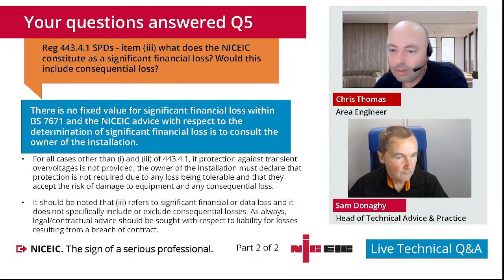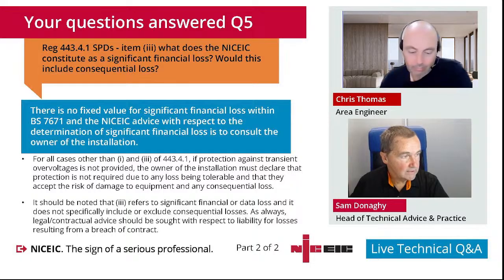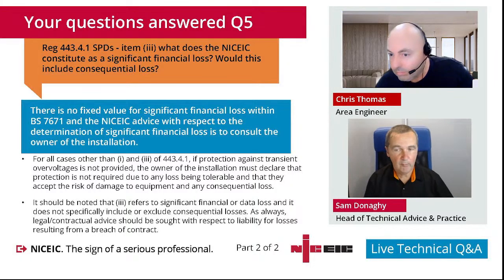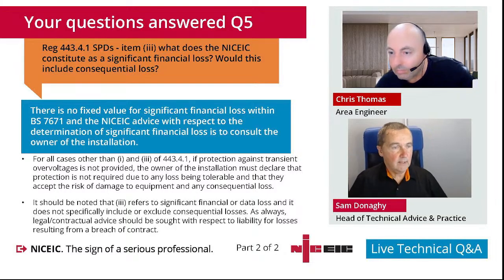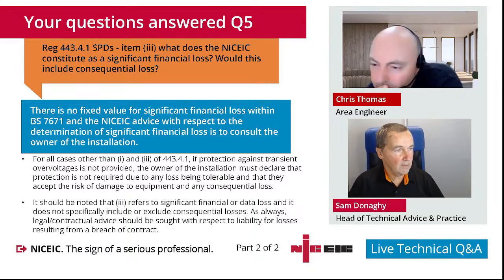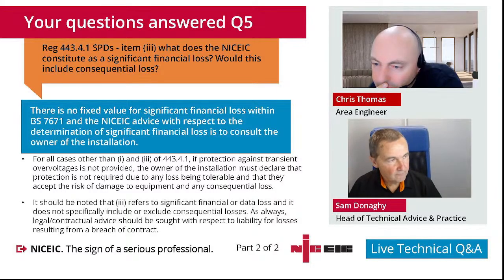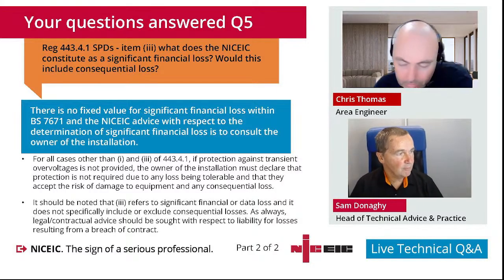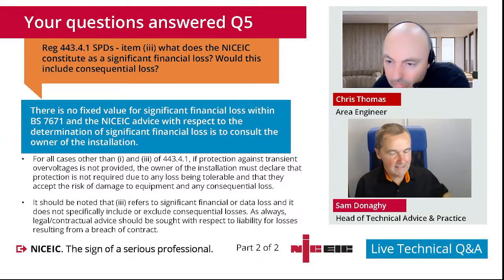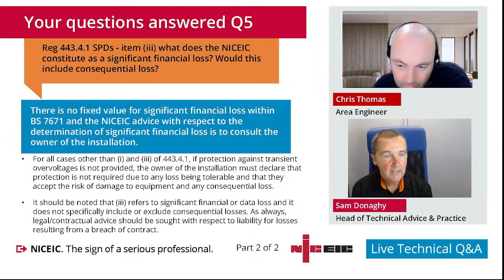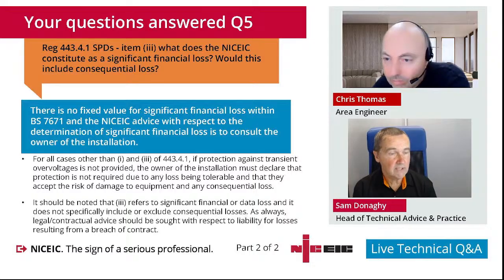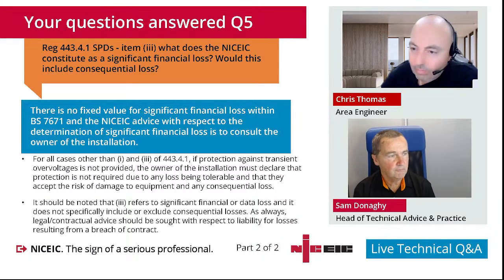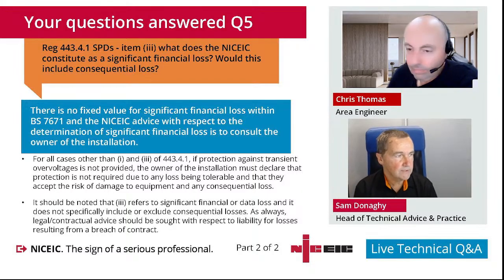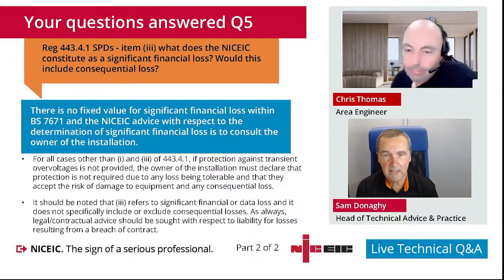Okay. Absolutely. Some of the questions that are coming through. The first one that is a little bit open, but I think it's something that we can try and put a response to. So very open. Can I use 2.5 mil twin and CPC in conduit? Few questions I'd like to ask as to what's the purpose and why we're doing that. But in general, no issues with using twin and earth in conduit.